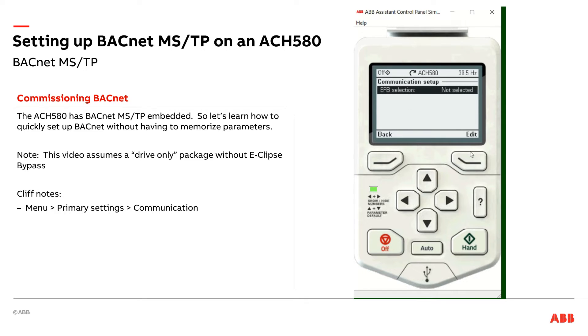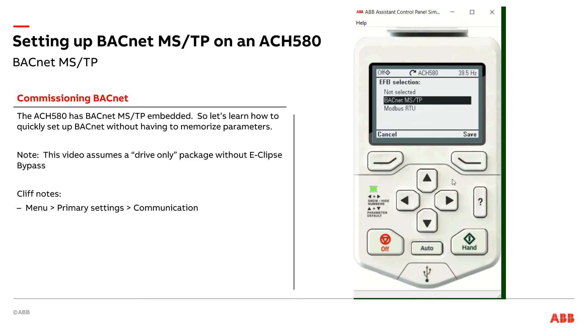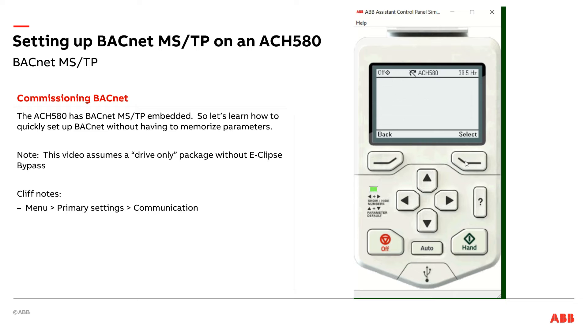The drive has BACnet MSTP built into it, and also has other protocols like Modbus built into it. So I'm going to go ahead and select BACnet MSTP, hit Save here, and we're getting the drive ready for BACnet.